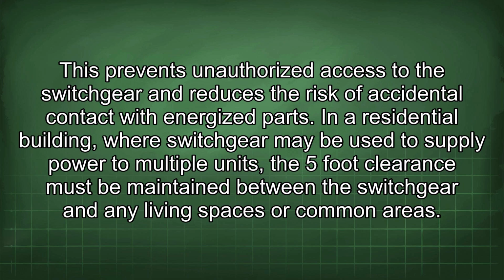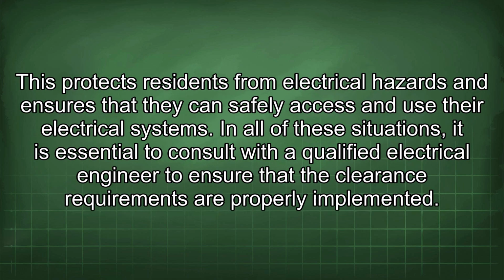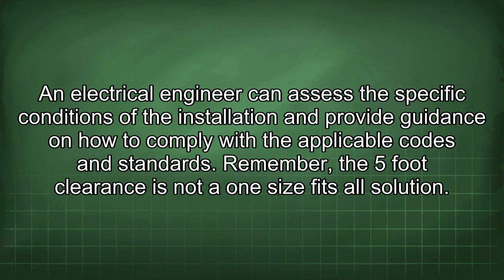In a residential building, where switchgear may be used to supply power to multiple units, the 5-foot clearance must be maintained between the switchgear and any living spaces or common areas. This protects residents from electrical hazards and ensures that they can safely access and use their electrical systems. In all of these situations, it is essential to consult with a qualified electrical engineer to ensure that the clearance requirements are properly implemented. An electrical engineer can assess the specific conditions of the installation and provide guidance on how to comply with the applicable codes and standards.